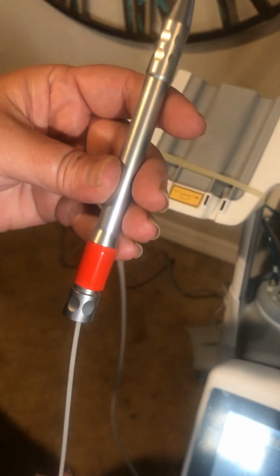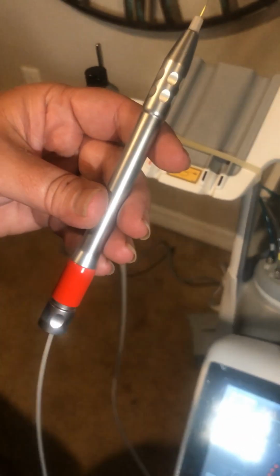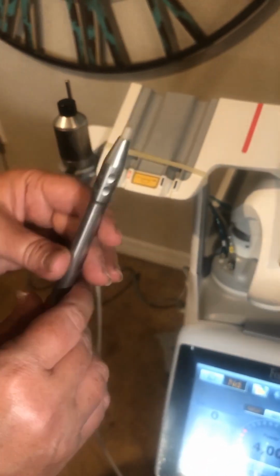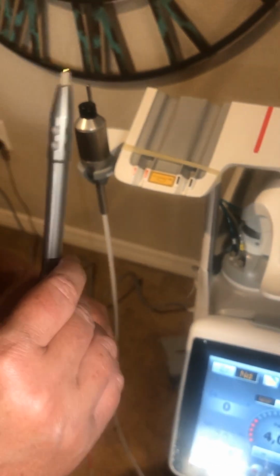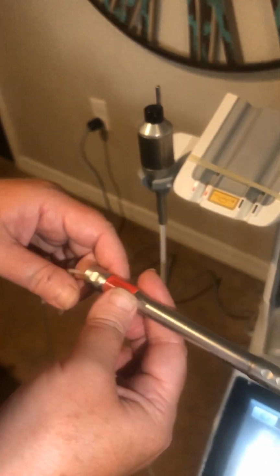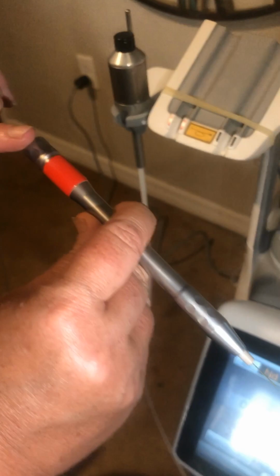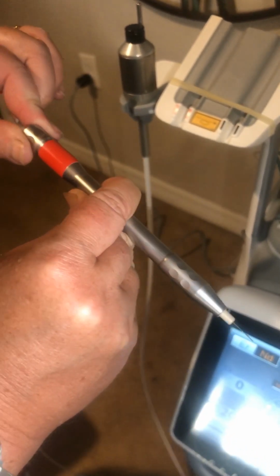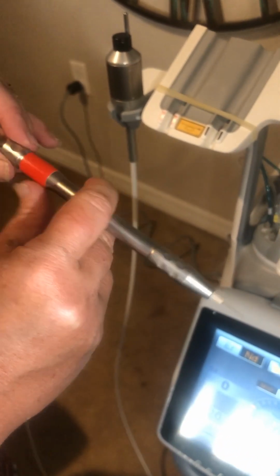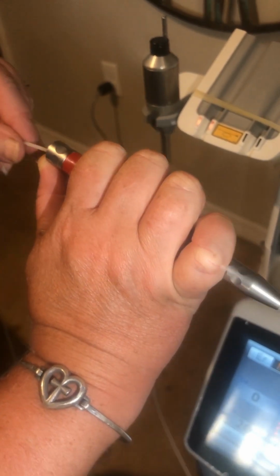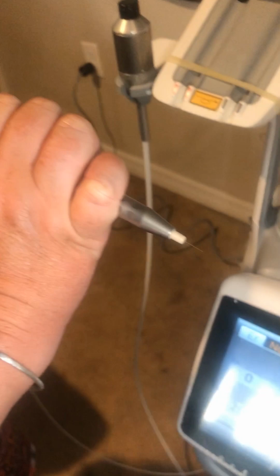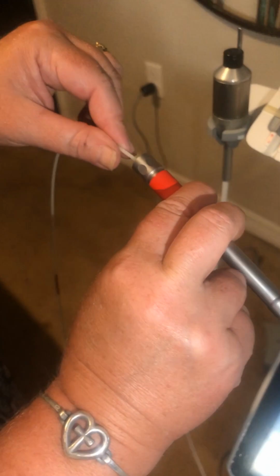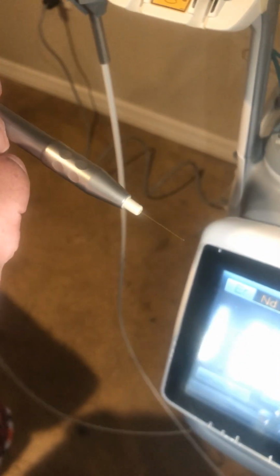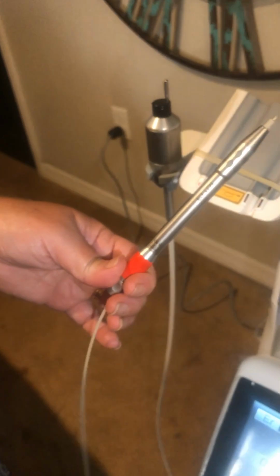Now the fiber is very, very thin, and it's extremely fragile, so you want to pay attention to it, and that's why we have this little attachment here so that we can kind of keep it protected. When you're using it on this handpiece, this end part here pushes in and out. That is the part that actually is the locking mechanism. So if you're holding it like this and you pull it with your thumb, it's going to allow that fiber to move in and out of the handpiece. Okay, so when you release it, it locks in place, and there's no more movement that's allowed. Okay, so that's how that works.